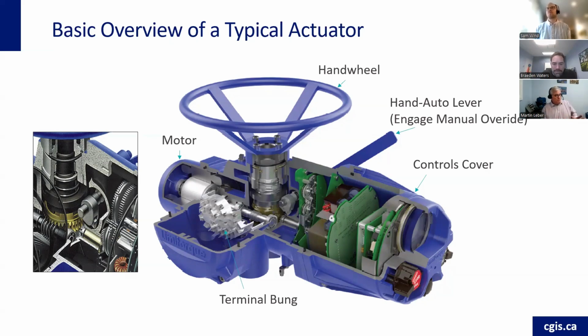So it has an electric motor, built into the housing of the actuator. We have a hand wheel and a hand-auto lever. Why a hand wheel? In the event of a failure with the actuator or a loss of power, the valve can still be actuated through the hand wheel. You engage this hand-auto lever, and once engaged, the motor is decoupled and the hand wheel is engaged to the drive sleeve, so you can open and close the valve manually.